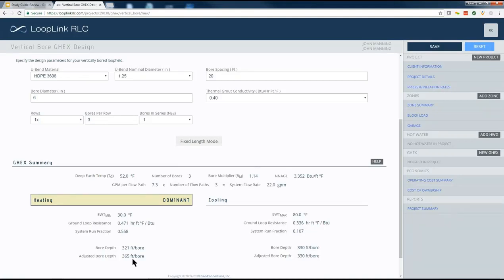And basically what you're doing there is you're giving each bore access to more soil, more volume for thermal energy storage, and it mitigates that ground load imbalance effect that we were seeing because this is such a heating dominant system. Another thing you might be able to play around with is the thermal grout conductivity. Notice that we've got a drop down here. It shows all of the options, but a 0.4 grout is generally a standard non-thermally enhanced grouting product. It's as simple as it gets.